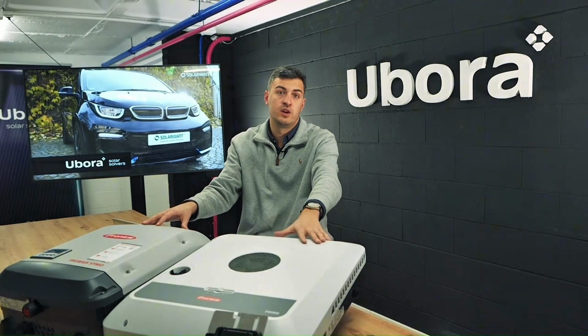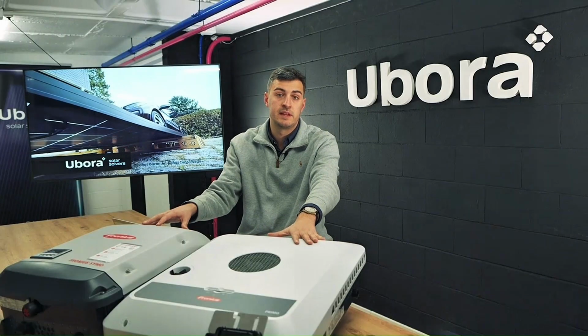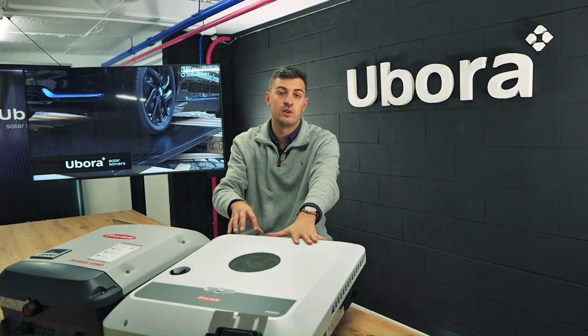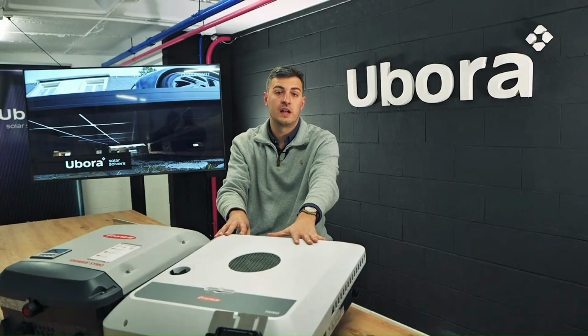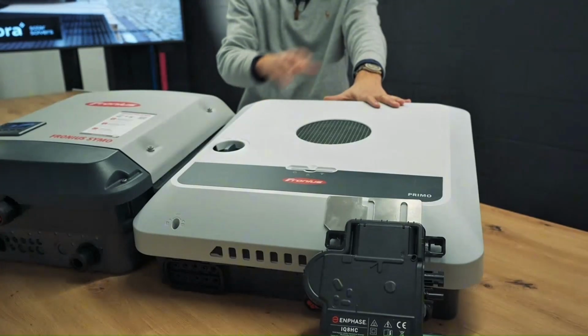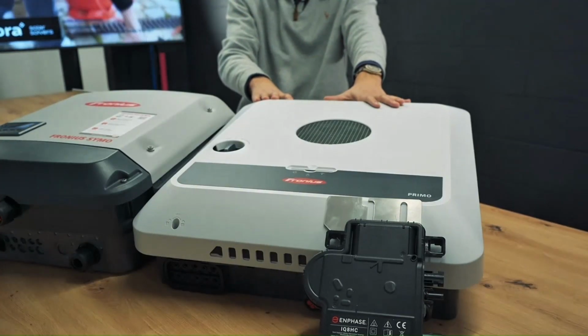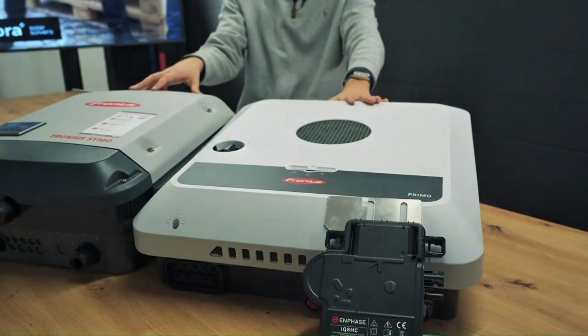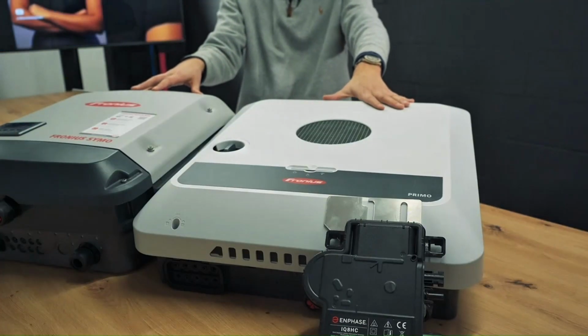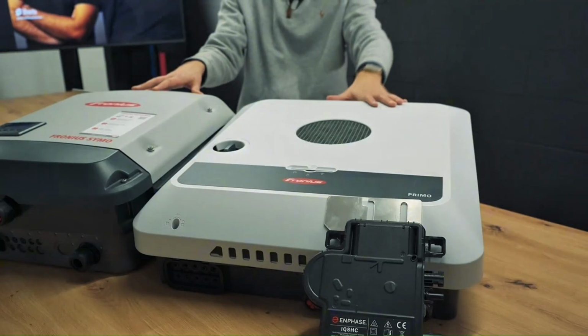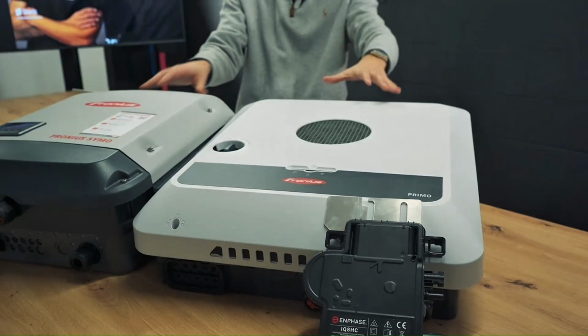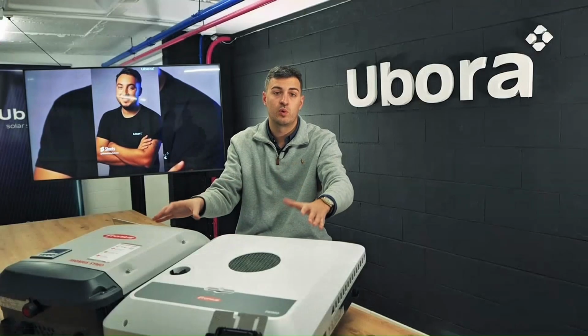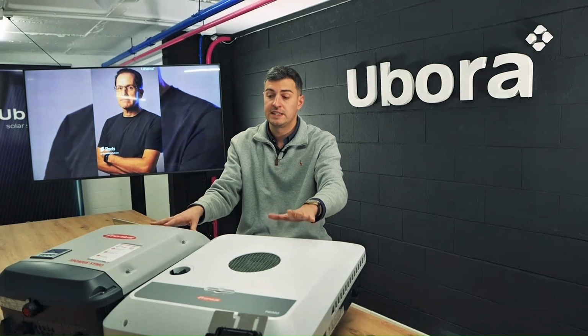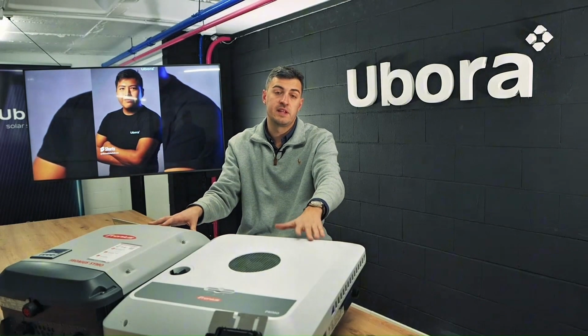If our home's electrical installation is three-phase, we cannot install a single-phase unit because we would simply be integrating the installation into only one of the phases and would unbalance the house's phases. And in your case, if we had a three-phase electrical installation, we could install a single-phase configuration, but we would be talking about the same thing. We would be installing only on one of the phases, so the installation would not be balanced.